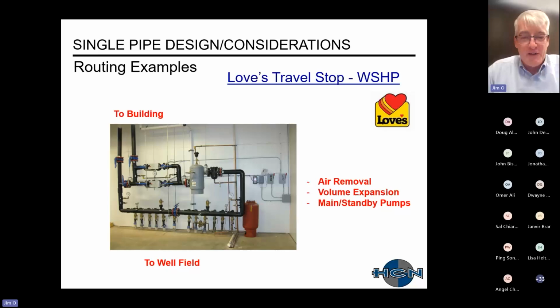Apologize for my color blindness or just terrible description of colors, but sitting on the ground on the lower right, like an orange or reddish brown thing, is an expansion tank. In the center there is an air separator. You can't see it, but there are 2 circulating pumps, and then the piping goes up to the building in the upper left. This project with the water source heat pumps was using a well field, and there's all that at the bottom going through the floor, all the individual branch piping that goes out to the well field. So there's a supply and return, et cetera.